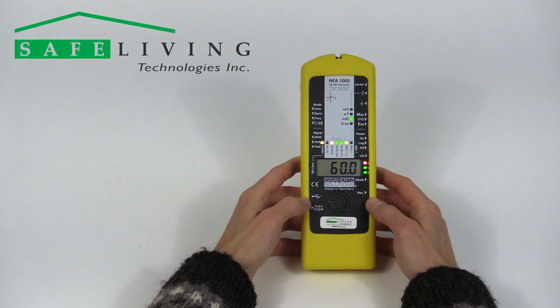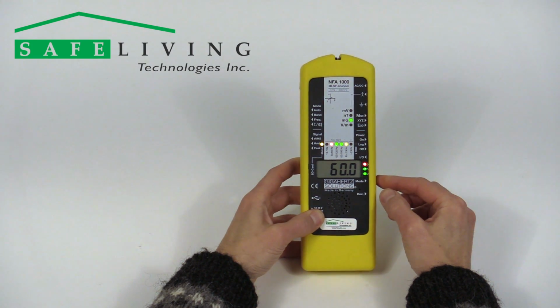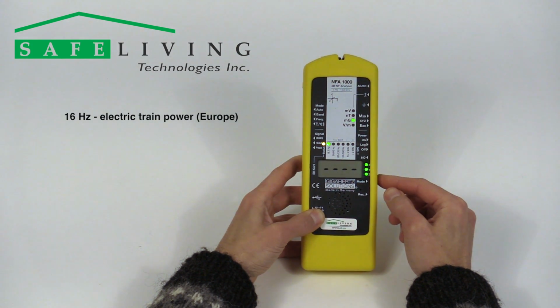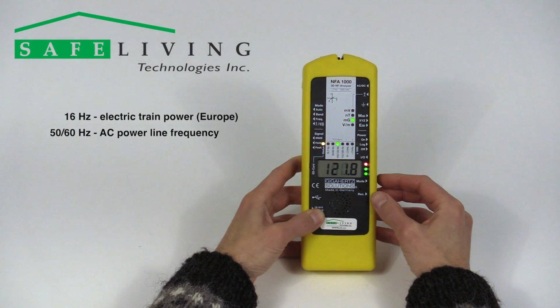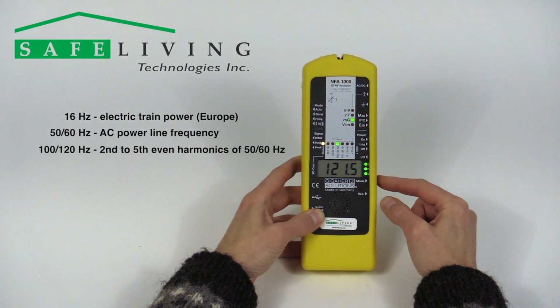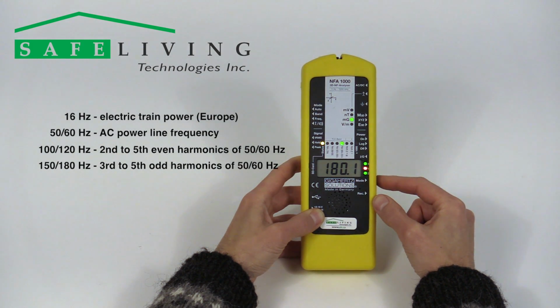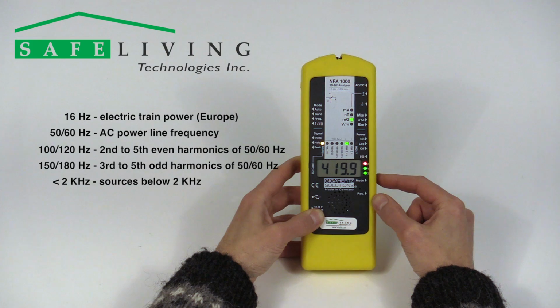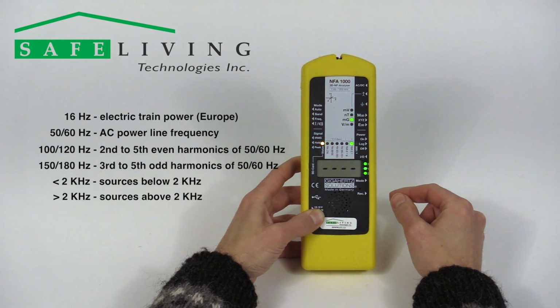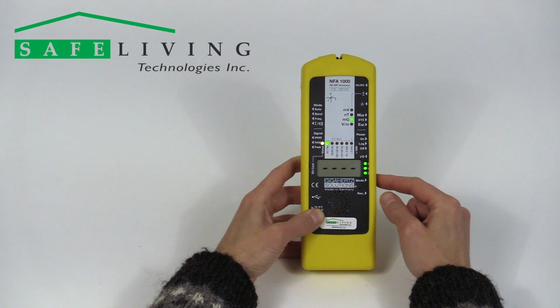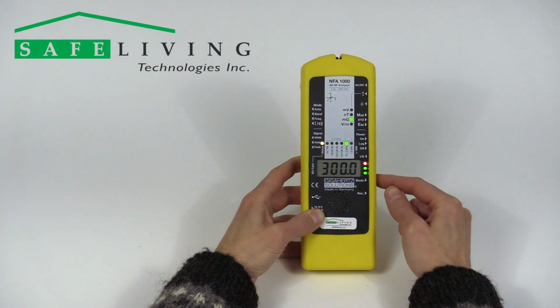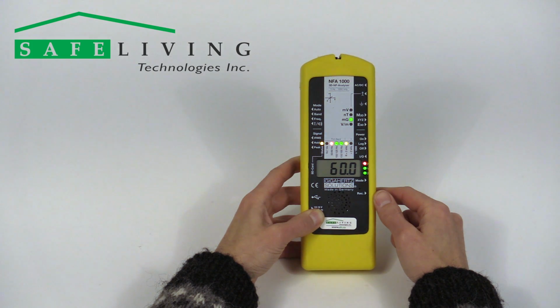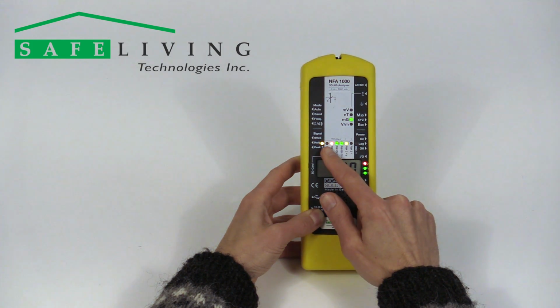To limit the band or frequency range to which you would like to see the actual frequencies, use the mode push button to cycle through the bands as described earlier: 16 Hz, 50 or 60 Hz, 100 or 120 Hz plus harmonics, 150 or 180 Hz plus harmonics, everything below 2 kHz, and everything above 2 kHz. Other operational modes are available through NFASoft. Note that if a band is disabled in the meter's NFASoft configuration settings, the corresponding LED will not illuminate. More details about this will be described in our Datalogging and NFASoft video.